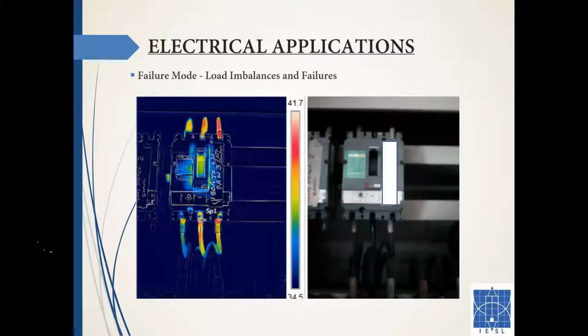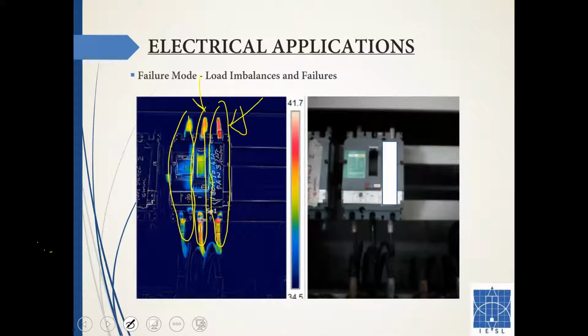This is another classic image. You can see these three terminals are of three different colors. This one is really red, this one is red but not as red as the first one, and this one is really cold. So you see a classic load imbalance situation here. What you do is propose to the client that you need a load balancing survey and balance out the loads. This is not necessarily a terminal problem, it's a load-related problem that can be more difficult to resolve.